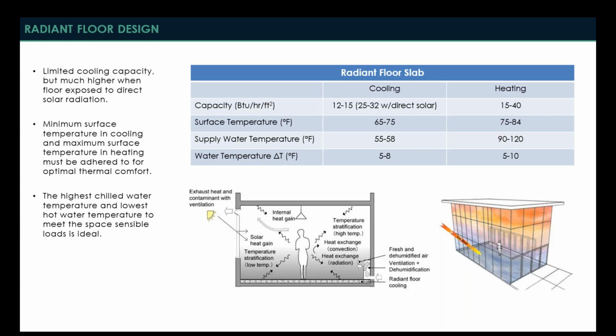Typical supply water temperatures for radiant floor slabs are between 55 and 58 degrees. And again, that's quite a bit higher than you would see in a traditional all-air system, which might use anywhere between 40 to 44 degree chilled water. On the heating side, again, a little wider band of temperatures that are possible, but usually between 90 and 120 degrees. We find that around maybe 110 or 115 seems to be the sweet spot between energy efficiency and maintaining that maximum temperature. And you're also looking at smaller water temperature delta T's for a radiant floor slab system.